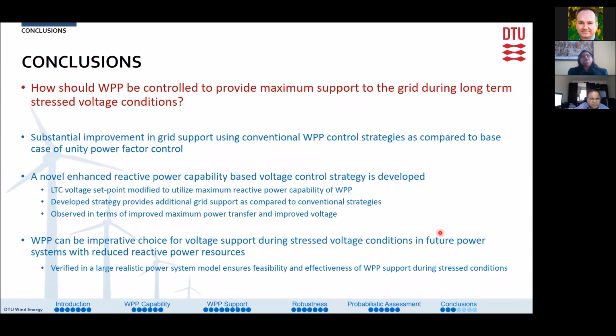The second question was, how should a wind power plant be controlled to provide maximum support to the grid during long-term voltage stress conditions? We see that using conventional wind power plant control strategies during stress conditions substantially improves the grid voltage compared to the base case of unity power factor control. Also, a novel enhanced reactive power capability based voltage control methodology was developed, which provides additional grid support compared to the conventional strategies.